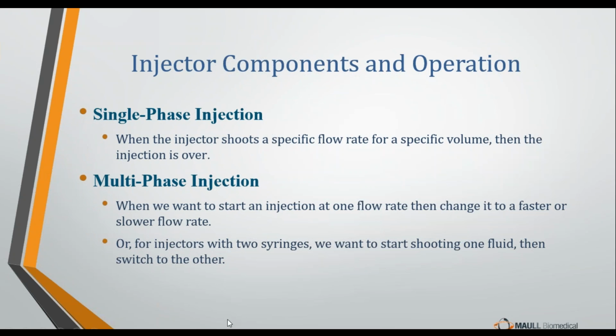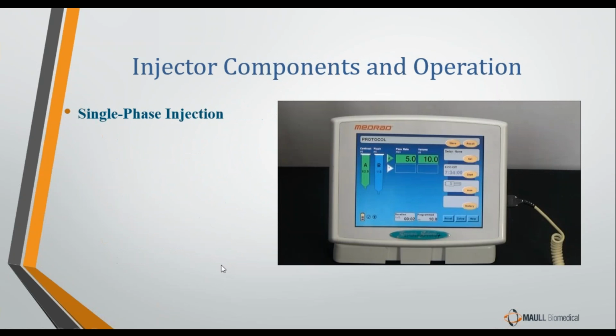Now, that is not to be confused with something called a single phase and a multi-phase injection. These are two different things, obviously. A single-phase injection is when the operator wants to shoot a single injection at a specific flow rate for a specific volume, and then the injection is over. A multi-phase injection, we'll show examples of this in a second, is if we want to start the injection off at one flow rate, then change to a different flow rate after we've started, or if we have an injector with two syringes, a contrast syringe and a saline syringe, we want to start the injection shooting one fluid, then switch over to a different fluid. All right? Now, this is a single phase injection right here.